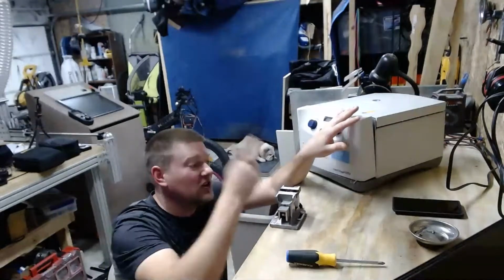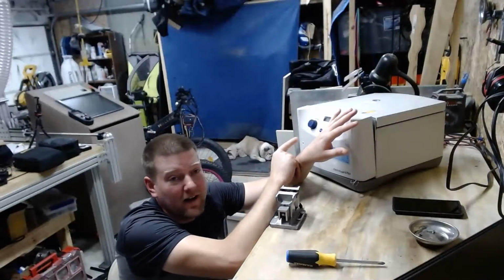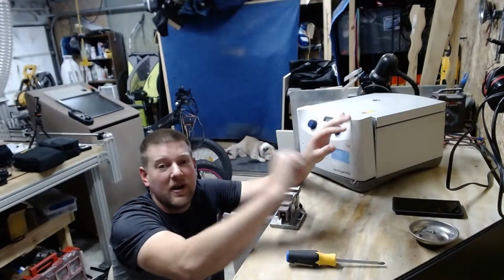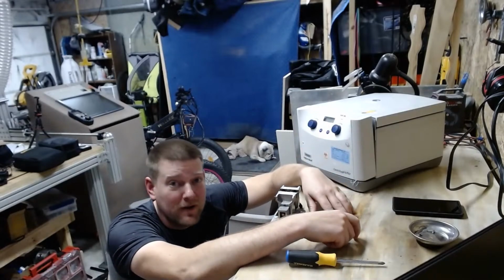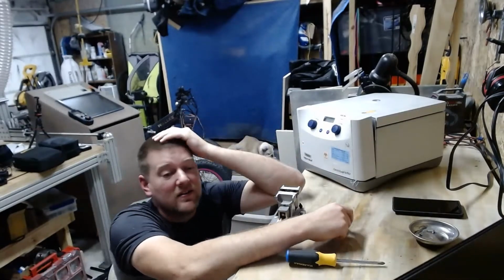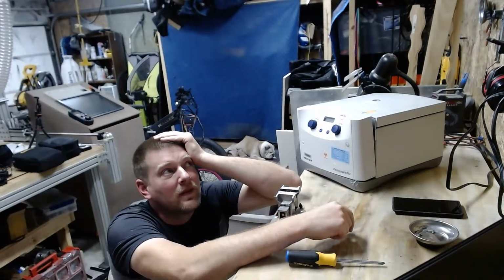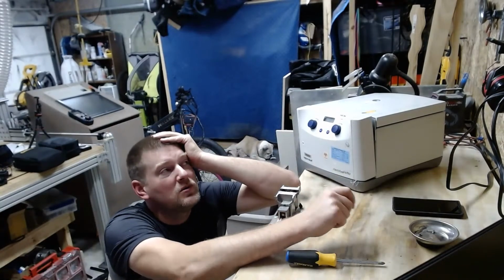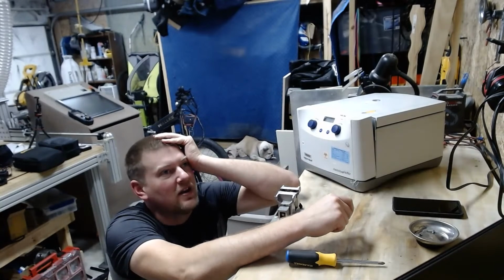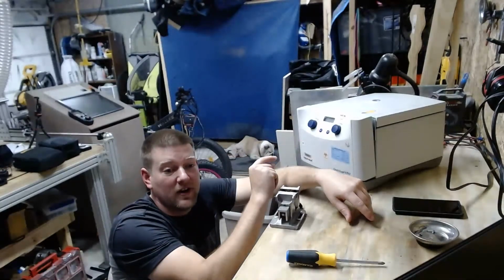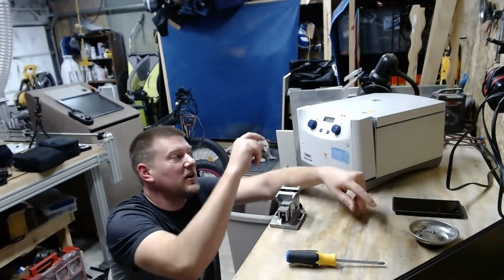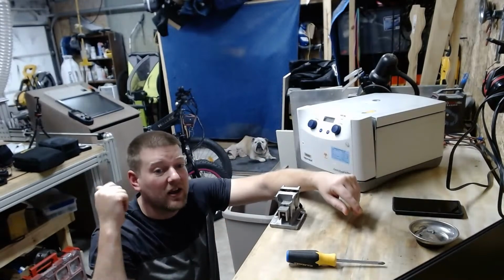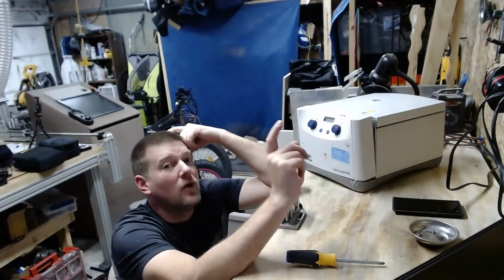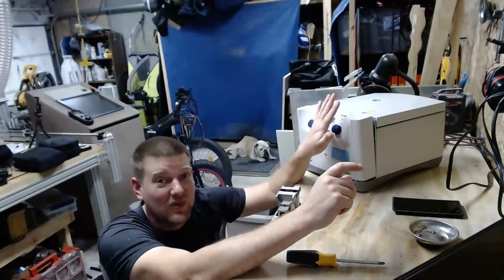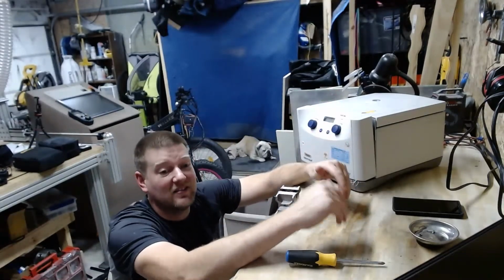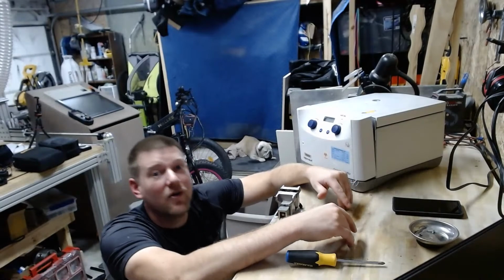That means the amount of minutes and the RCF or RPMs. Write it down before you touch anything, because unfortunately these don't reset themselves often when you shut the power off. Like I shut the power off on this one and it was at 4,500 RPMs. You turn it back on, guess what, it wants to sit at 4,500 RPMs. The users, they're not stupid, but users are users, man. They want to walk up to a device they've been using every single day, hit the start button, and walk away, especially in a laboratory.